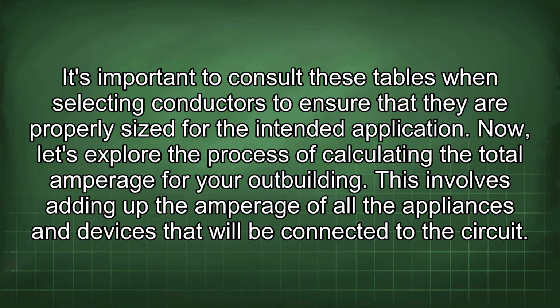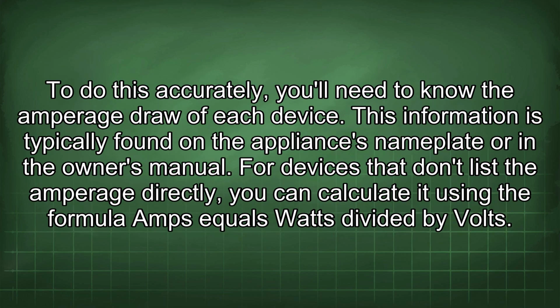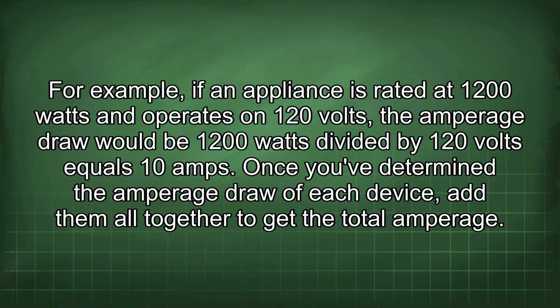Now, let's explore the process of calculating the total amperage for your outbuilding. This involves adding up the amperage of all the appliances and devices that will be connected to the circuit. To do this accurately, you'll need to know the amperage draw of each device. This information is typically found on the appliance's nameplate or in the owner's manual. For devices that don't list the amperage directly, you can calculate it using the formula amps equals watts divided by volts. For example, if an appliance is rated at 1200 watts and operates on 120 volts, the amperage draw would be 1200 watts divided by 120 volts equals 10 amps.